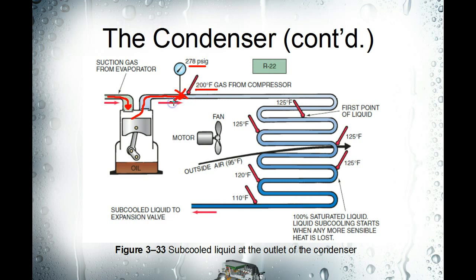Right at the outlet of the compressor you're going to have 278 psig and 200 degree Fahrenheit gas coming from the compressor. If you look at your pressure temperature chart, that doesn't match up — because the pressure temperature chart only deals with refrigerant that's in the saturated state, where it's going to change from vapor to liquid.